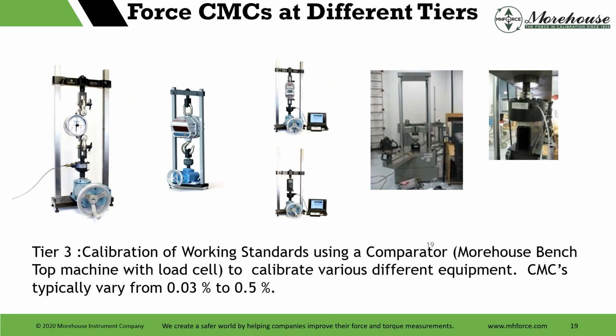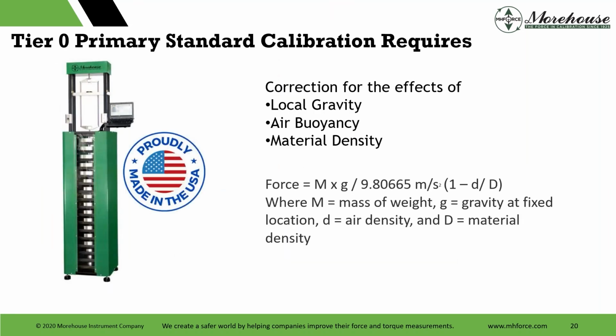And then tier 3, calibration and working standards. There we have a bench top with load cell, different equipment, and CMCs typically vary 0.03 to 0.5% on a testing machine. Talking about the weights and what you would do, at tier 0 you have weights calibrated hopefully by a really good reference laboratory. In our case, it's NIST, though there are several mass labs out there, even our state can adjust and correct for local gravity, air buoyancy, and material density. You have to give them that information, and you have to give them that target weight. So there's some calculation that you may need to do.